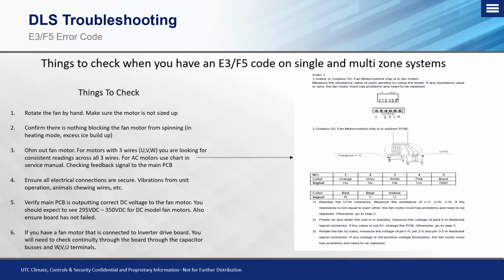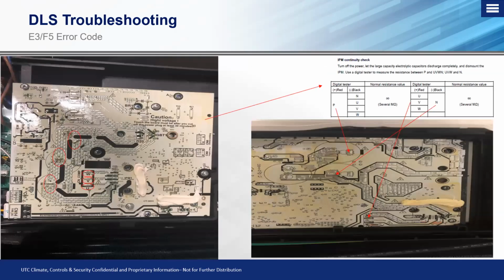Okay. But finally, what do we do, or what can we do to check that inverter drive board? Because we know how to check the main board, we need to see DC voltage output. But there's a little bit more to that drive board that we can troubleshoot and confirm if there is an actual issue. So here's what we're going to do. On these boards on the back side, this is what you're going to see here. Now on the left side is the split type, or where we have a main PCB and then a separate inverter drive board with that heat sink on there. And typically your outdoor fan motor and your compressor connections feed directly back to that.